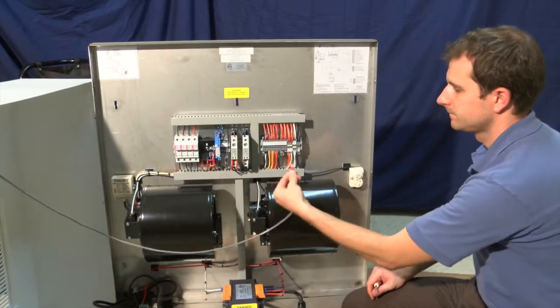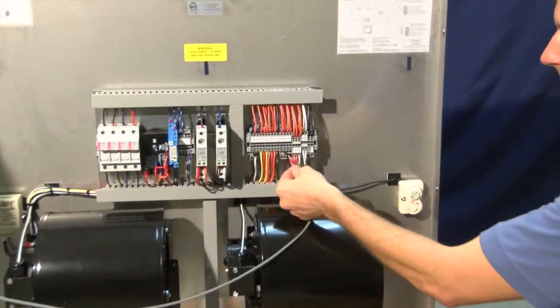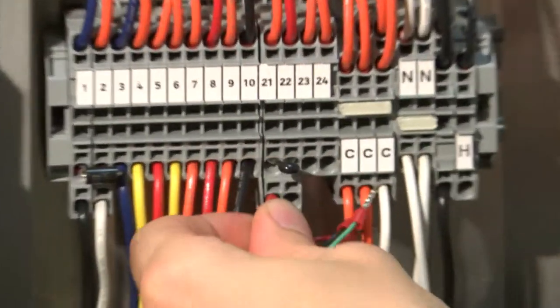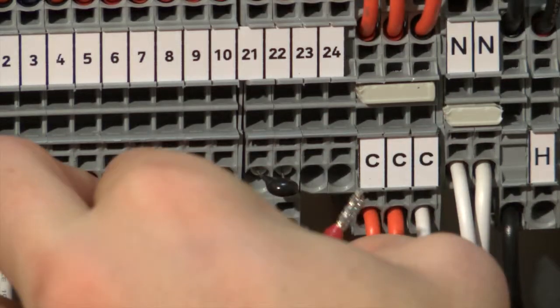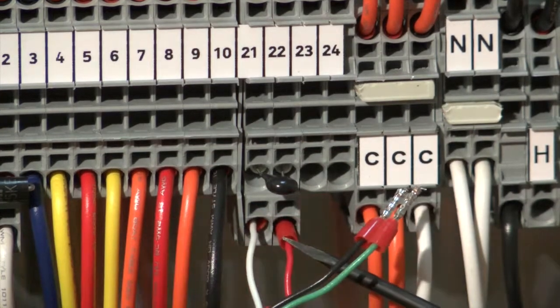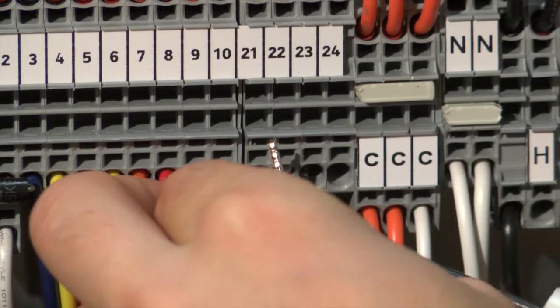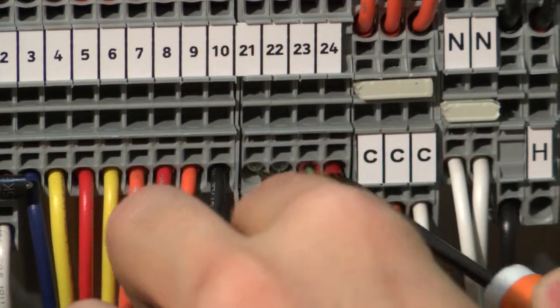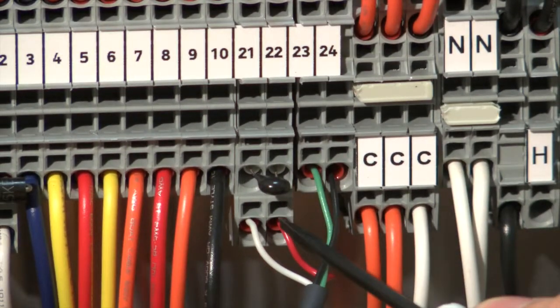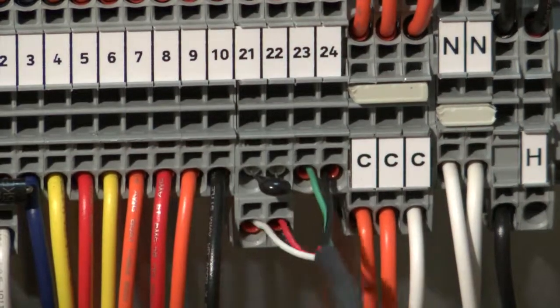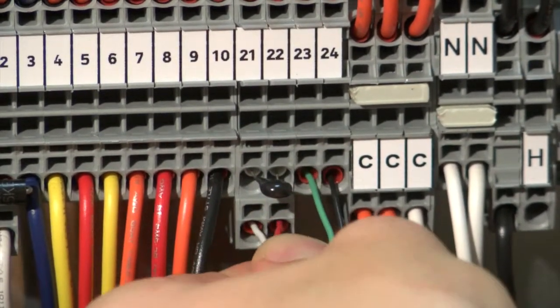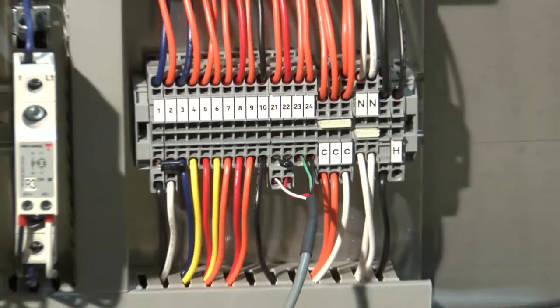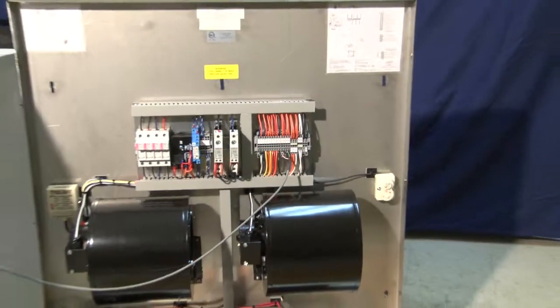At this point, reattach your humidistat wires per the wiring diagram. The 4 wires will be replaced in order white, red, green, black. To reinstall a wire, simply use the same Tek screwdriver you used to remove it and press the ferruled end into the clamp terminal. The clamp terminal will automatically secure the wire. After all wires are in place, give them a small tug test to make sure they are securely held. Your unit is now ready to run with its new transducers.